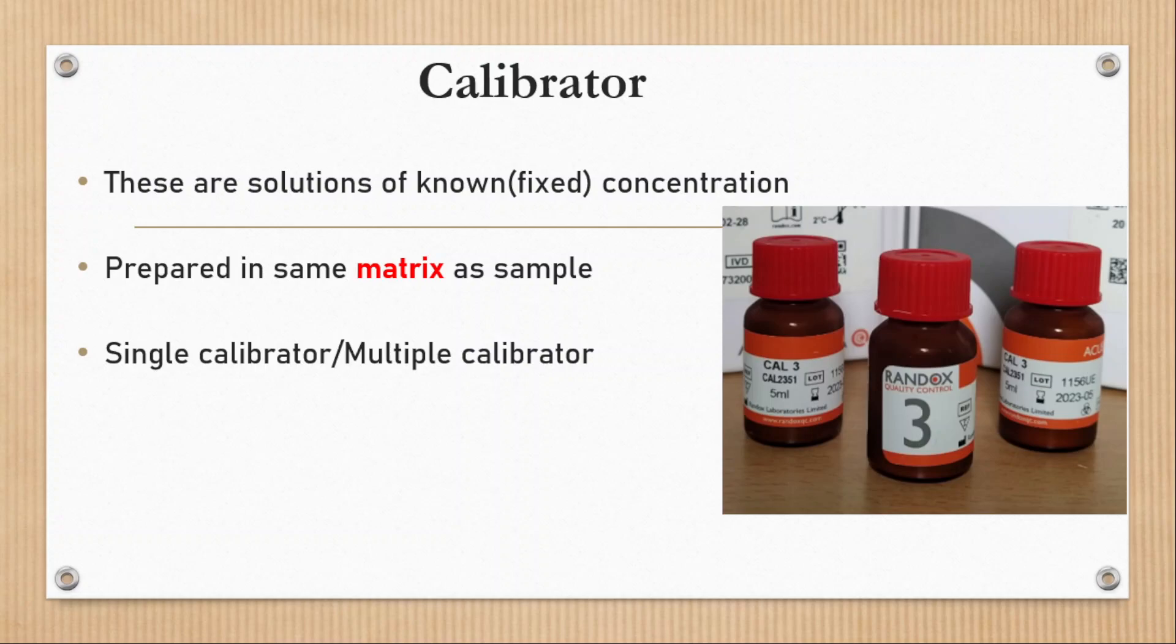Coming to the definition, calibrators are the solution of known concentration or fixed concentration prepared in matrix same as sample. That means if sample is plasma, then matrix of calibrator is also same as plasma. Calibrators are supplied through manufacturer either in liquid or in lyophilized form.